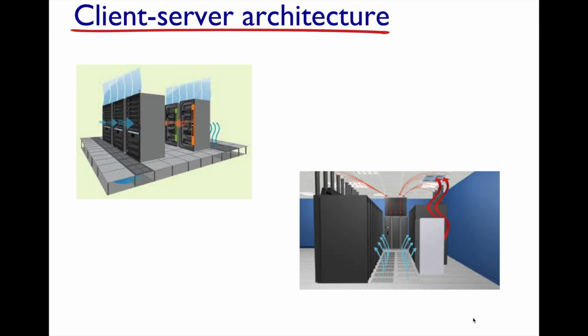Another thing these facilities do is have so-called raised floors. You have the actual floor, typically a raw concrete slab, then some metal framing, and some support and flooring above that. There's an air gap underneath the floor you walk on, and cold air is pumped into that gap, with vents coming up in front of the rows of units, pushing air out the back and pulling air in through the front.